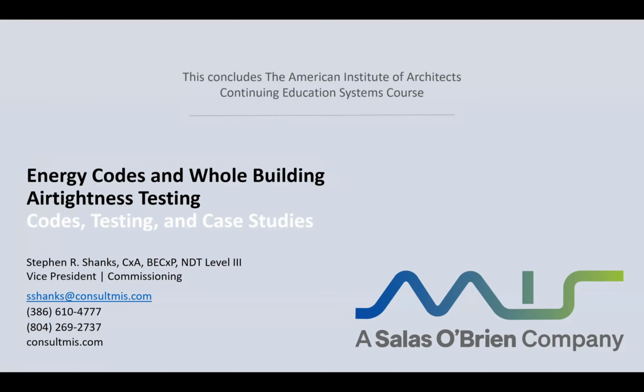So we do that under test. First thing we'll typically do before running the multi-point regression and everything is pressurize the building to see if it's going to be a failing or passing test. We get that pretty quickly. And if it looks like it's going to be failing or close, then we'll go ahead and do some diagnostic testing at that point to see if it's a fault in the as-constructed condition or in the masking condition. That's also a benefit of doing the earlier phased testing in areas where you expect you may or may not have a problem, just to verify that.